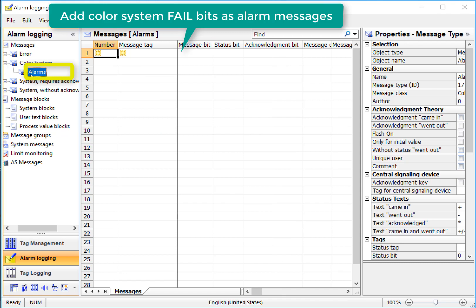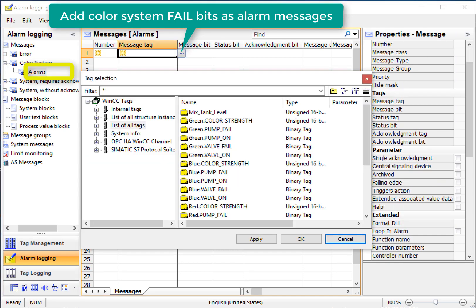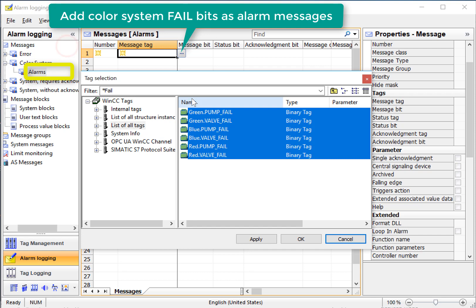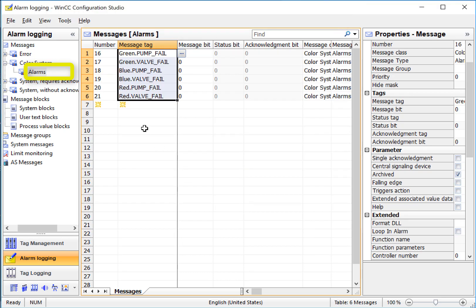Going back to our alarm system, we'll create alarm messages from our fail tags for pumps and valves for each color system. On the first line, I will open the tag browser, and I can use my filter to find the tags that we want. So here's all of our fail tags for our red, green, and blue systems. I will lasso to highlight them and just click OK, and it's created alarm messages for each tag.